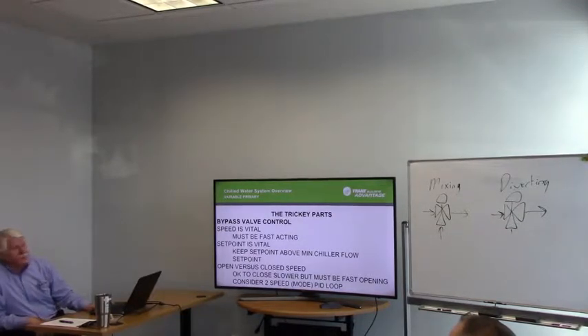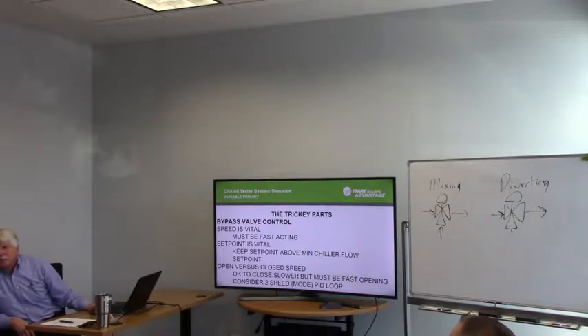Open versus closed speed. This is one thing you can do something with. It's okay to have it close slowly, okay? Because that's just reducing flow. But when the chillers need flow, it has to open fast, okay?